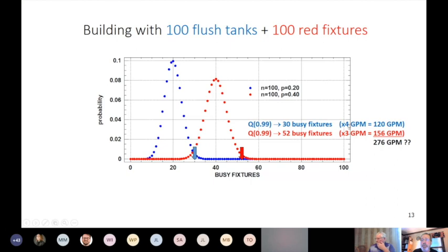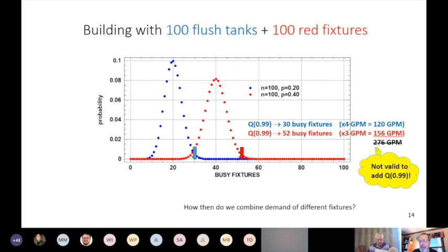Oh yes, I've got the blue coming in at 120. But what do I do with that? Do I add both of those values together to get my design discharge at 276 GPM? It turns out that is not the correct way to approach this, and Hunter recognized that.